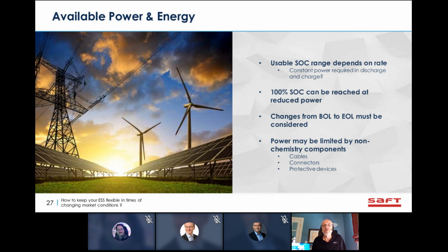That can mean we're limited not just at the low end for sustaining a discharge, but also at the high end where we can no longer support constant power in charge. We can reach 100% state of charge, but at reduced power if that's acceptable for the application. And that usable state of charge range will vary over the battery life.